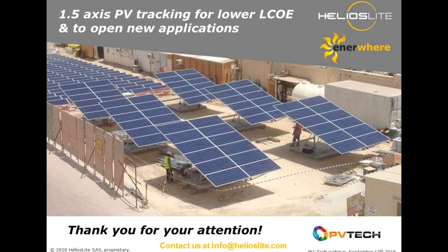What is the optimum DC:AC ratio for a 1.5 axis tracker? For a normal fixed rack PV plant, developers have had the tendency to oversize the DC side slightly, because it's very rare that you're actually producing at the peak rated capacity of the system. With trackers, we typically recommend doing a 1-to-1 ratio. So if you have a 1 megawatt field of PV, I'd recommend also doing a 1 megawatt inverter, with no undersizing of the inverter.